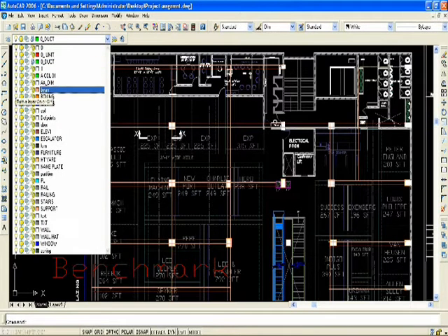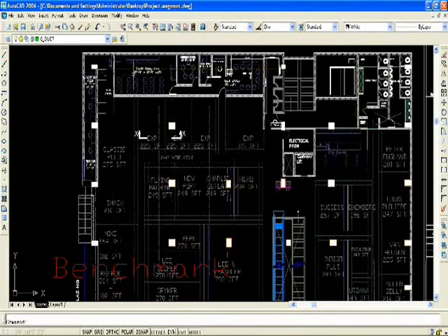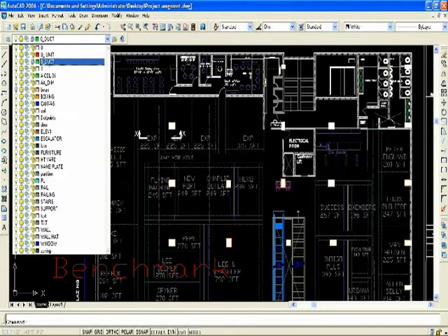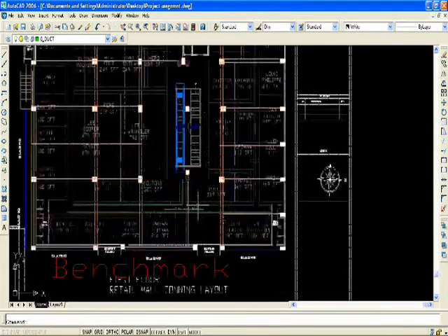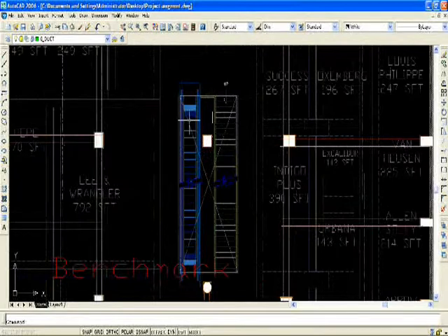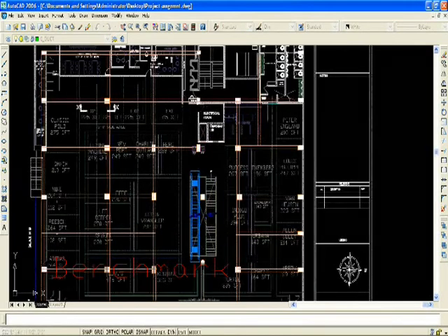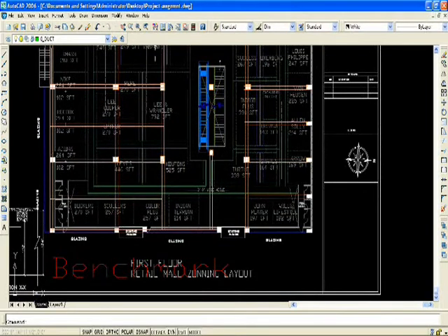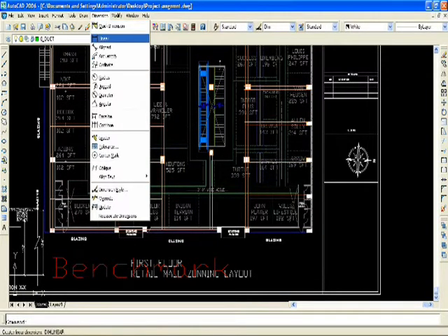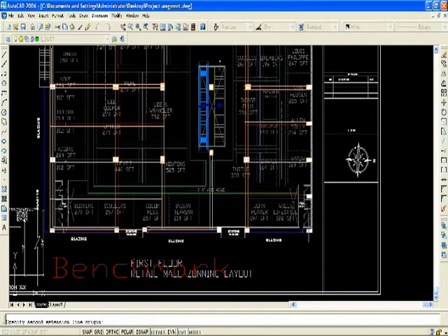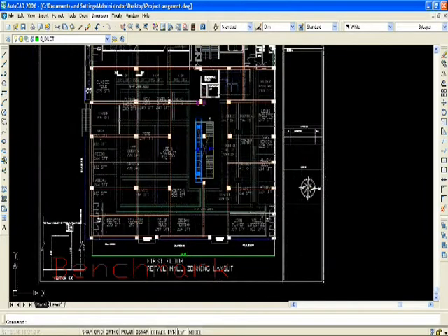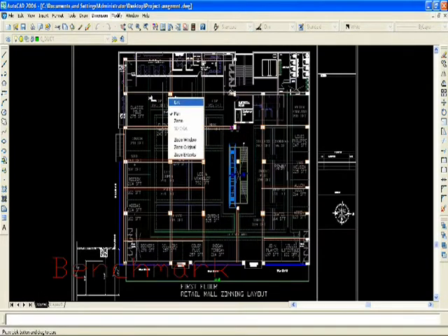We have around 13,000 square feet of area. We'll consider occupancy of around 430, which is normally 25 square feet per person for retail projects. For lighting, we are considering 2 watt per square feet, and also some CPU based computers and equipment load, along with some miscellaneous sensible and latent load for our preliminary cooling calculation. These are the units we have to feed in our software. We are considering a 0.15 bypass factor and a blow-through type unit, where the fan is after the coil. We have to use all this data in our calculation for the next step.